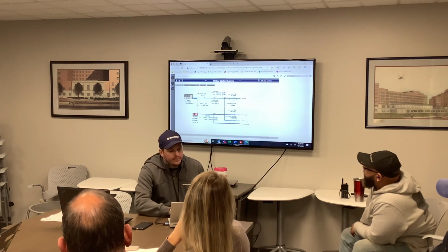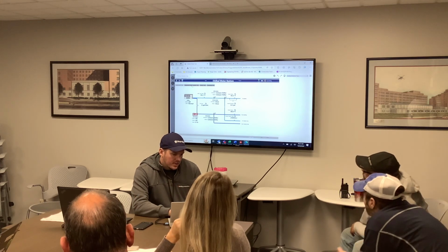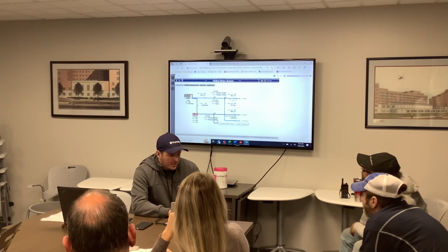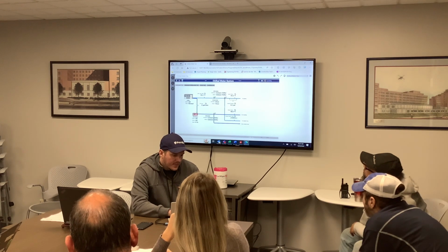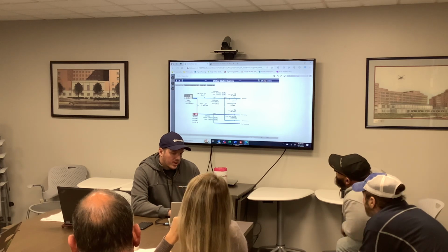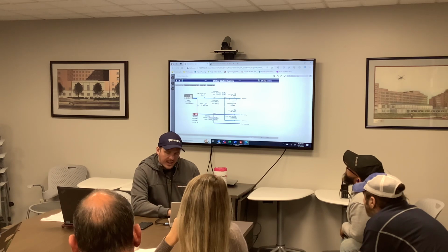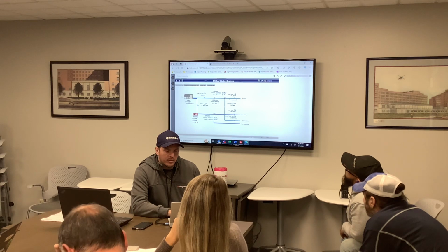Okay, chiller. So this is on the 6th floor. This feeds the endo wing. So this is pretty simple. You can see all the information just like you can on every other one. You've got your schematic, set points, notes, and trending. It's off right now. So when it's off, you have these two changeover valves, and what they do is they divert water from either the chiller, the 6th floor endo chiller as I call it, or the campus chiller. So right now, it's just pulling water from the campus chiller.